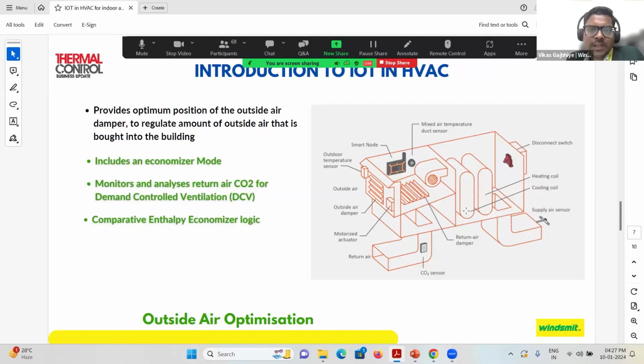On the basis of that, the return air damper and the outside air damper will be modulating. The third one is comparative enthalpy economizer logic.